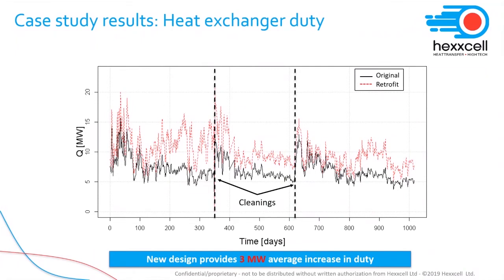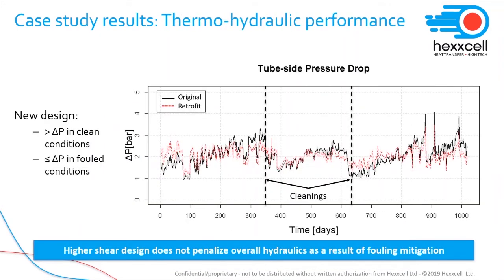Overall, the new design provides 3 megawatt average increase in the duty. If you look at the hydraulic performance, it's clear that the clean pressure drop in the proposed retrofits are higher. However, over time, because of the reduced fouling rates, the pressure drop in the proposed retrofit becomes actually lower than those in the original design.